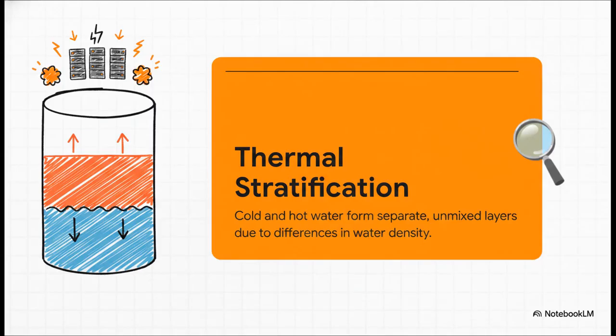Now, you might be wondering, wait a second, if we have perfectly cold water stored up for an emergency and boiling hot water constantly coming back from the servers, how on earth do we keep them from mixing in the tank and ruining our cold supply? Well, the secret here is a little thing called thermal stratification. This is a super elegant physical principle where cold and hot water naturally form separate, completely unmixed layers. It's just density. Cold water is denser and heavier, so it sinks right to the bottom. Hot water is lighter, so it floats on top.